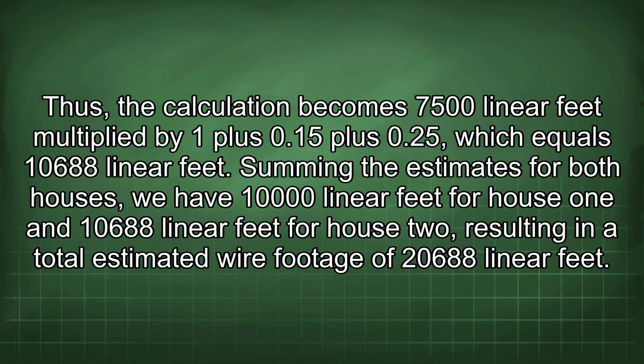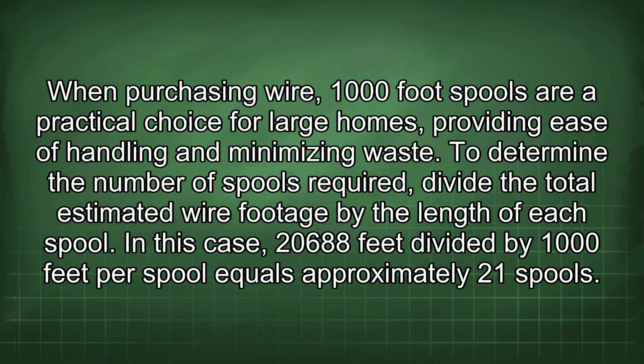10,688 linear feet. Summing the estimates for both houses, we have 10,000 linear feet for House 1 and 10,688 linear feet for House 2, resulting in a total estimated wire footage of 20,688 linear feet. When purchasing wire, 1,000-foot spools are a practical choice for large homes, providing ease of handling and minimizing waste. To determine the number of spools required, divide the total estimated wire footage by the length of each spool. In this case, 20,688 feet divided by 1,000 feet per spool equals approximately 21 spools.